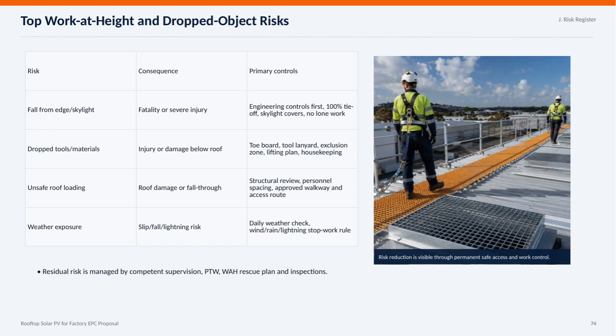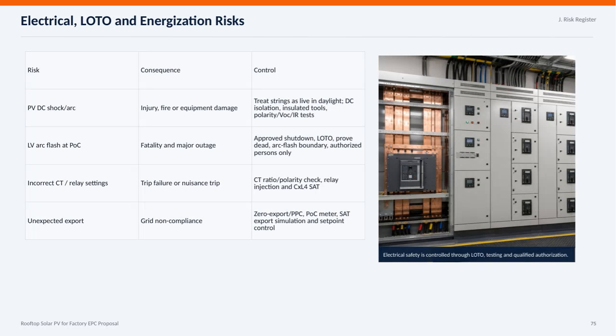at all times. Here we focus on the electrical, lockout-tagout, and energization risks associated with our rooftop solar PV proposal for the factory. The most critical risks include DC shock or arc hazards from the photovoltaic strings, which can lead to injury, fire, or equipment damage. To control this, we treat all strings as live during daylight hours, use DC isolation methods, insulated tools, and perform polarity, open-circuit voltage, and insulation resistance tests.